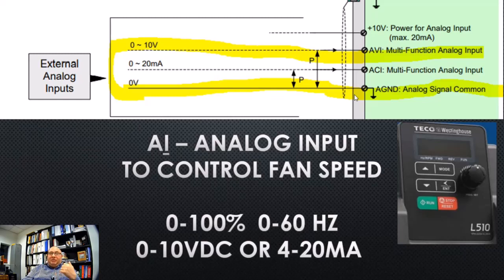If we were to use 4 to 20, we would then land the positive of the 4 to 20 here and the negative side of the 4 to 20 here. There are advantages and disadvantages to both signals. I would say at this point of your career, if you can wire it up with DC, it's better for all of us, because you could take a DC meter and read voltage across the line without drowning out the signal. If you're using 4 to 20, you have to measure it in series because it is a current signal. It's milliamps, and you need a special meter set on milliamps to read it.